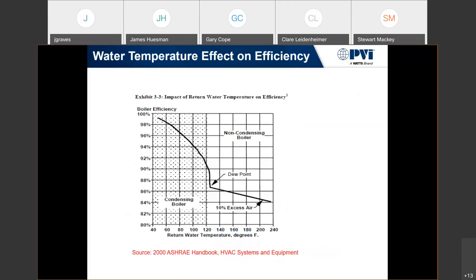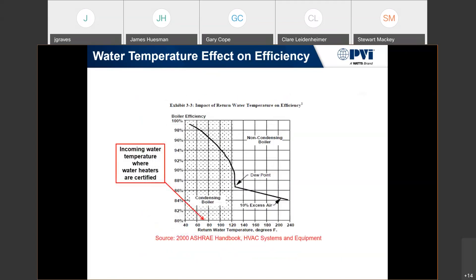Looking at the efficiency chart here, the x-axis is return water temperature and the y-axis is boiler efficiency. The higher the return water temperature, the lower the efficiency — because of that basic physics concept of cramming BTUs into the water. The more BTUs you can put in, the more efficient it is. That test standard is done at the 70-degree mark, which is why most efficiency ratings are in the mid-90s.